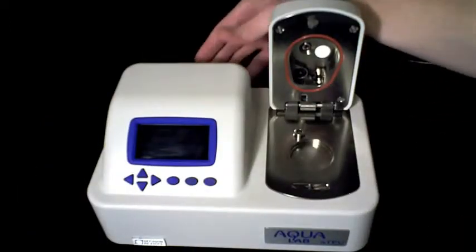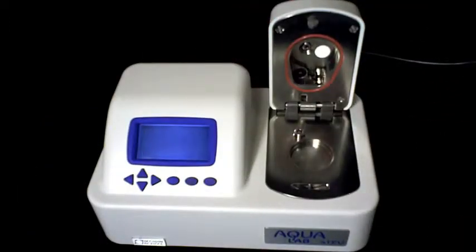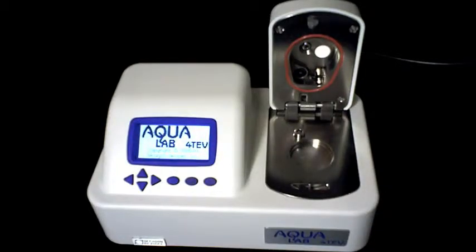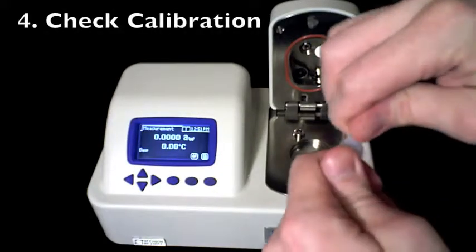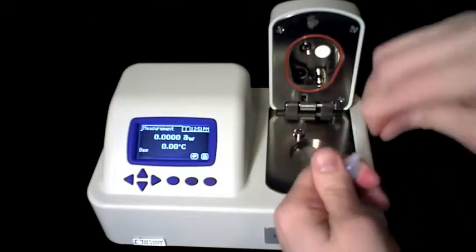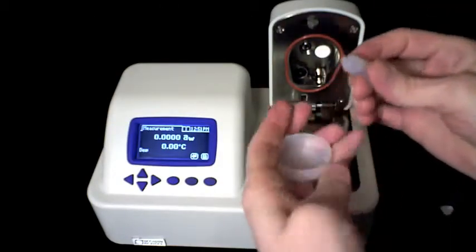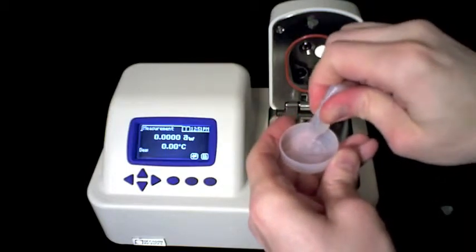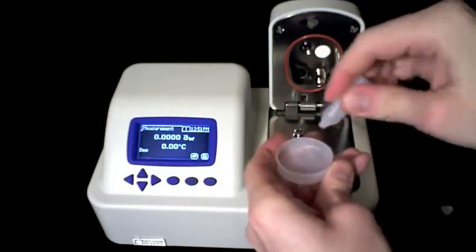After the cleaning process, it's important to verify that your instrument is operating properly. First, power your Aqualab back on. Then, take one vial of verification standards and put it in a sample cup. Place the sample cup inside the instrument, and close the lid.